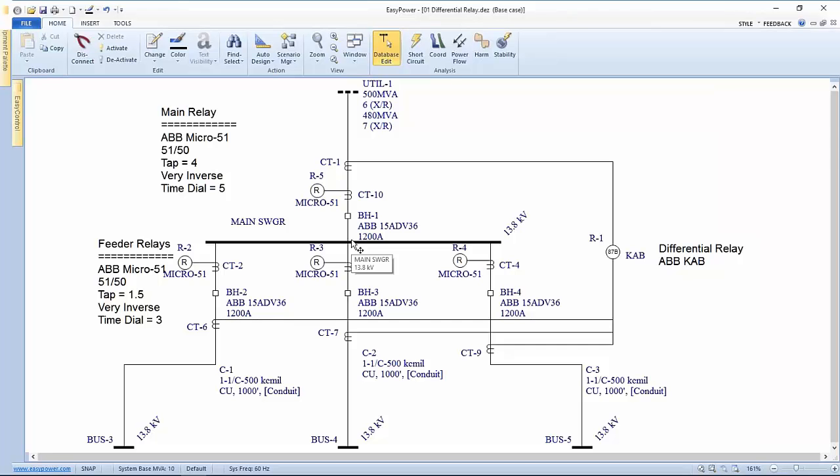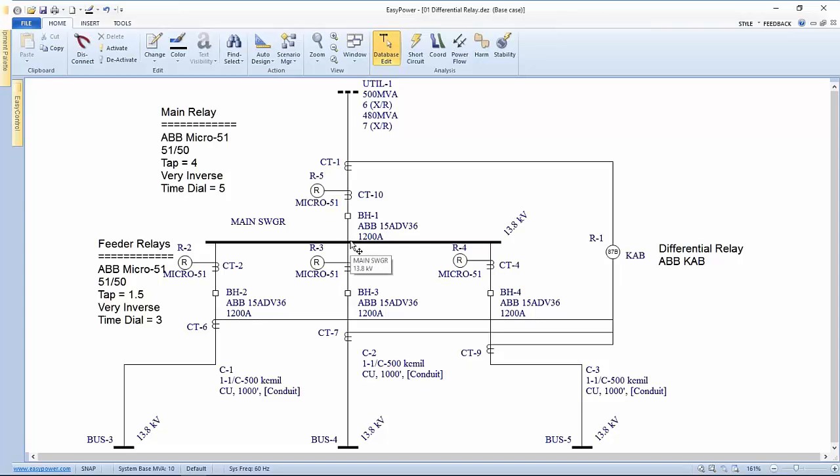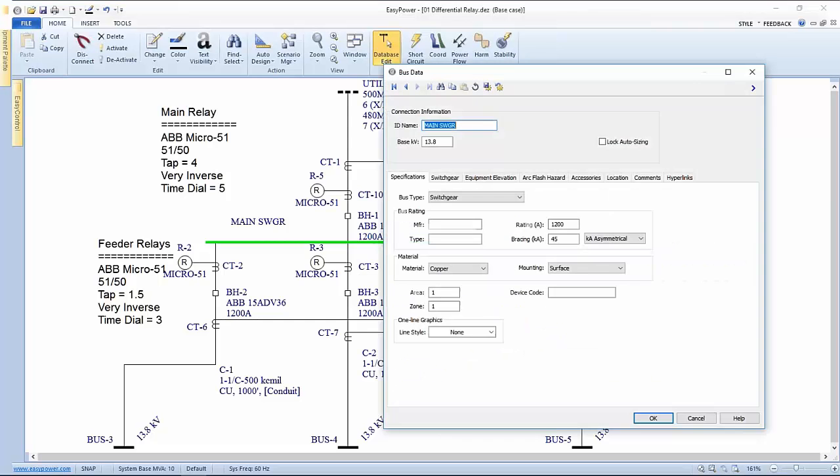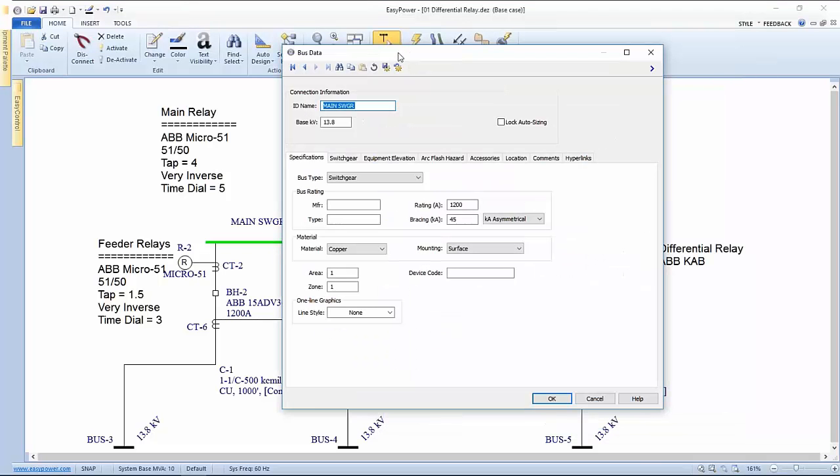The way EasyPower allows us to model this is we look at the bus that's most affected by the tripping unit. So it will be this upstream device. Consequently, the bus is directly downstream from the element that's going to be actuating. If we open up that bus, we define it as a piece of switchgear. It's all been set up as far as its rating.